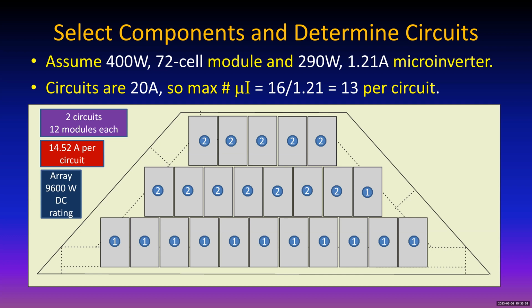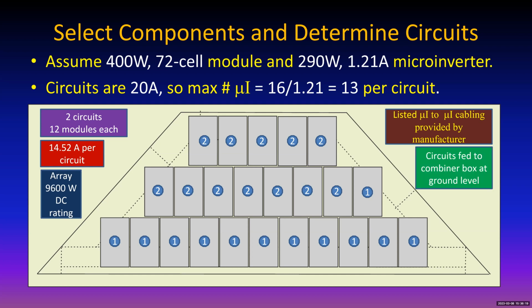We got 9,600 watt DC rating for the array. Listed cabling is provided by the manufacturer for hooking these things up, and they just snap together, and they're male-female type connections. You can be as drunk as you want and not make a mistake, but you got to be careful not to fall off the roof. And then these circuits are fed to a combiner box at the ground level.